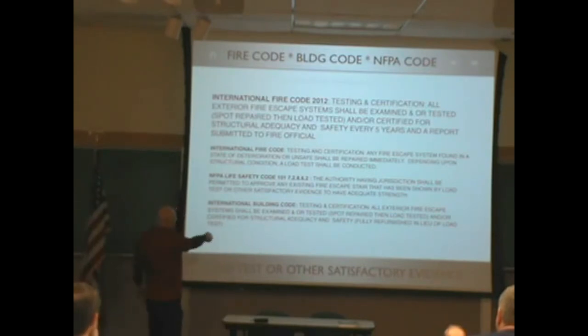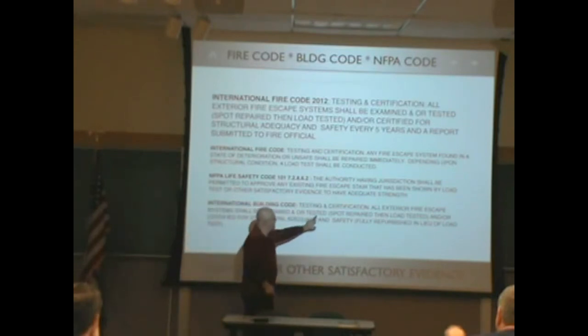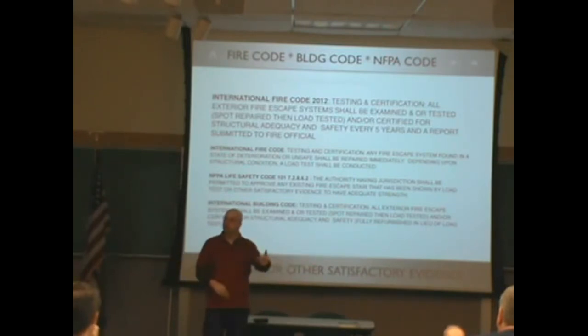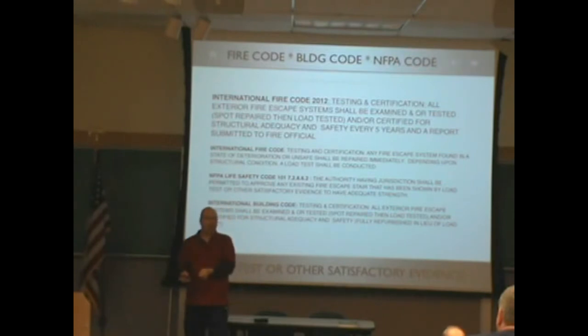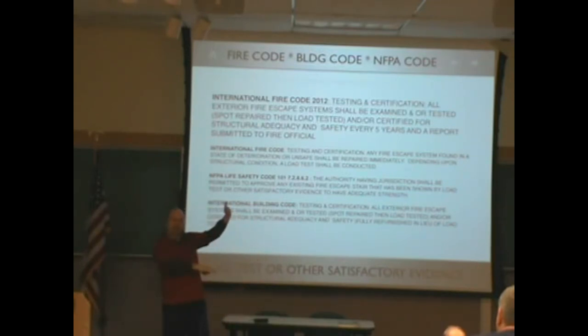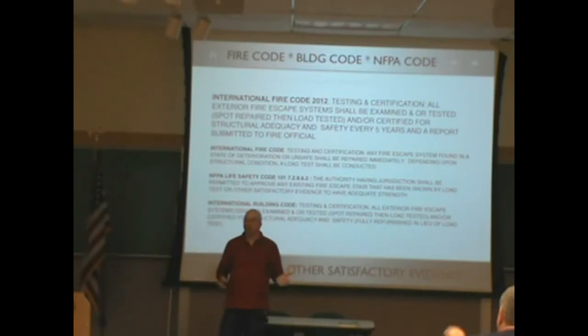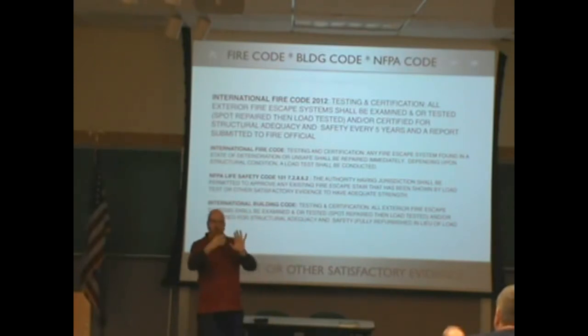Other satisfactory evidence does what to the load test? Nothing — which costs $3,000 to $5,000 a floor, depending on size and complexity. A five-story building, you're going to be blowing $15,000 to $25,000 to load test it. Why don't they use that money towards what really needs to be done? The NFPA says the authority having jurisdiction — 'depending upon structural condition, a load test shall be conducted.' Who decides that? The AHJ — Authority Having Jurisdiction. Sometimes you have to write that out; people start looking for some judge. That's you.